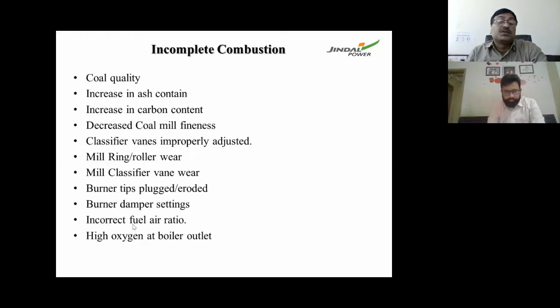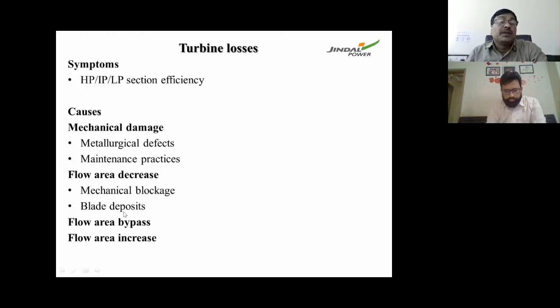Some of the turbine losses are in HP, IP, and LP cylinder efficiencies. Causes are mechanical damages like metallurgical defects, maintenance practices, and flow-related deposits. Some of the causes of deterioration are damage of blades caused by debris, damage to tip seals and interstage glands, and deposition on blades. Generally, it occurs on the last few IP stages and first few LP stages. The net heat rate is also affected by generator losses, which occur due to copper losses, iron losses, and other losses.